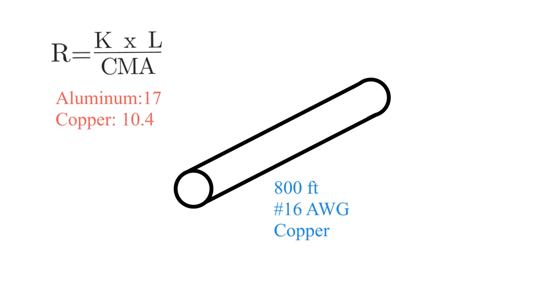So as an example, say this conductor here was 800 feet long of number 16 AWG copper conductor. So we have the length. We have our K because we know it's copper, so we'll be using 10.4. We don't have the CMA.